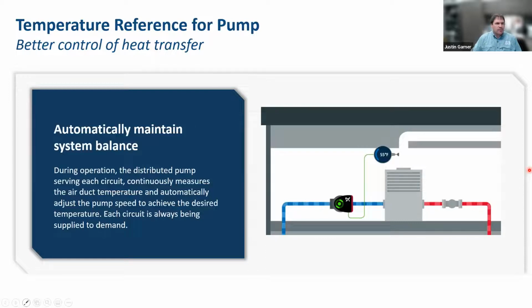While we don't do a traditional proportional balance on a setup such as this, you still have to have someone that's going to go through and verify the performance of the system. So this is just another pump in the system, just like the pumps that would be in your central plant or in other places in the system. You've got to verify their operation. We all know, I would imagine most folks on this call work in the industry and have a fair number of years of experience.